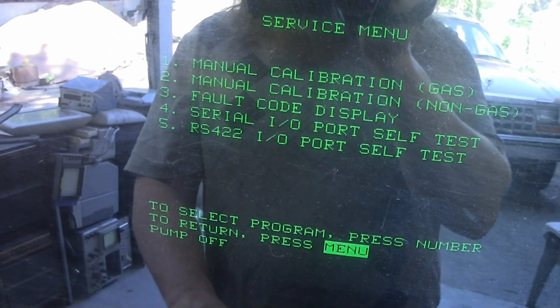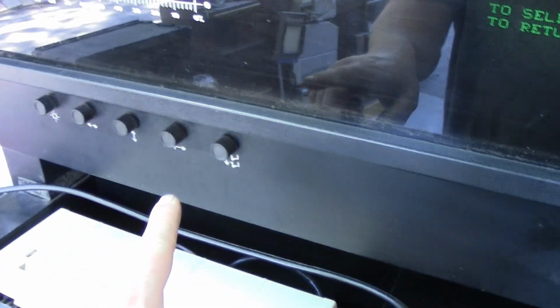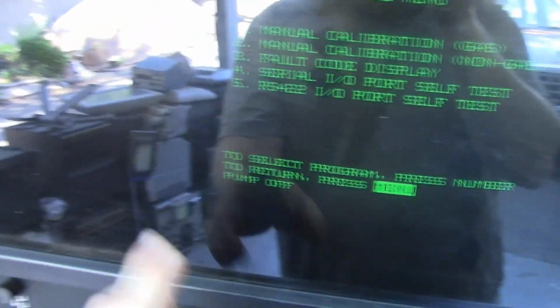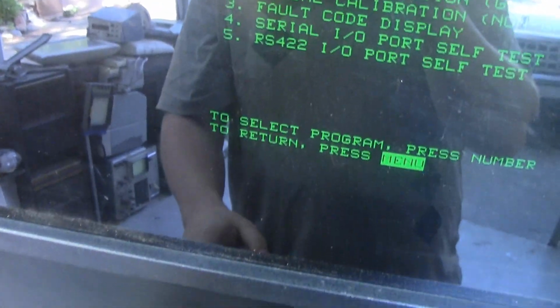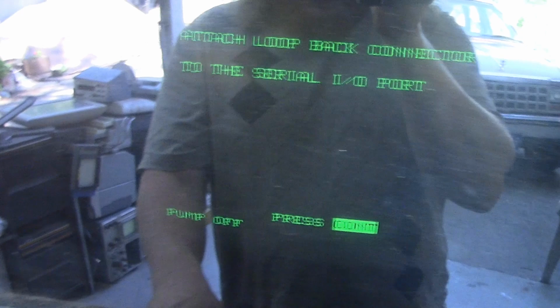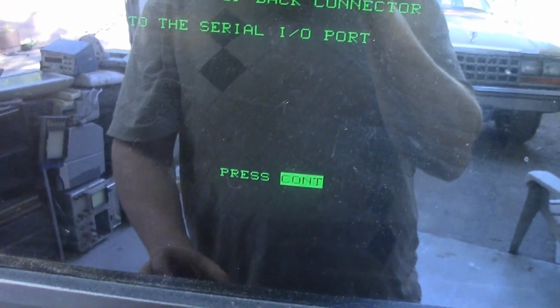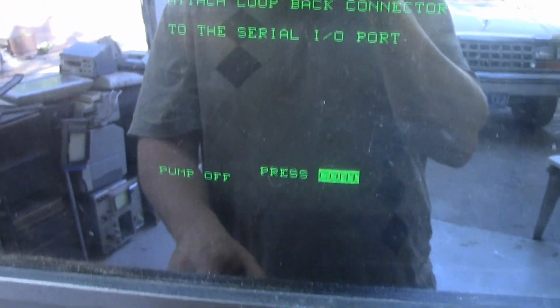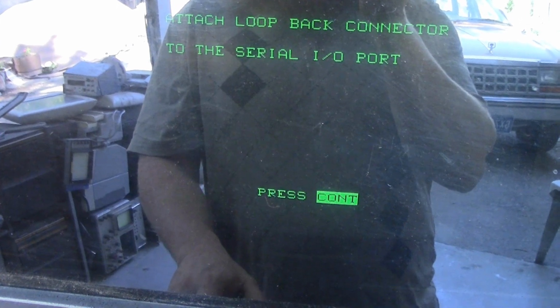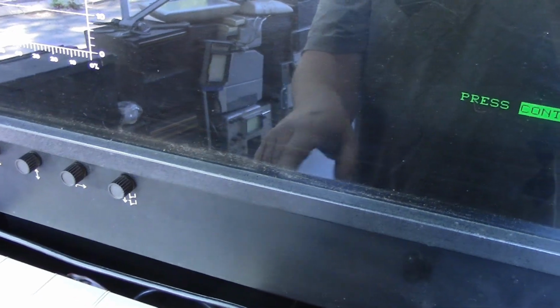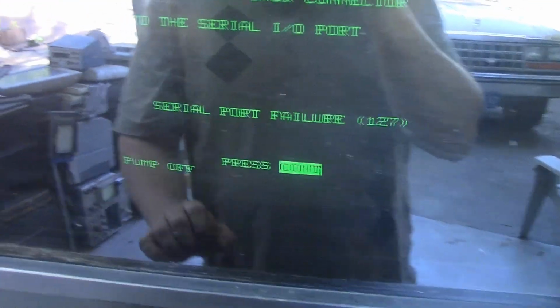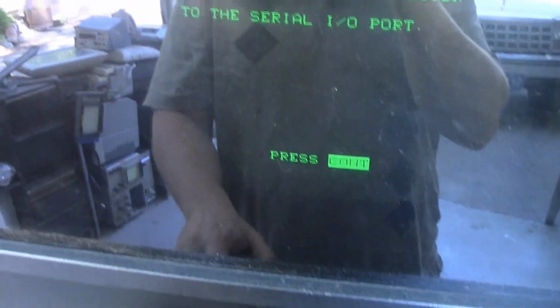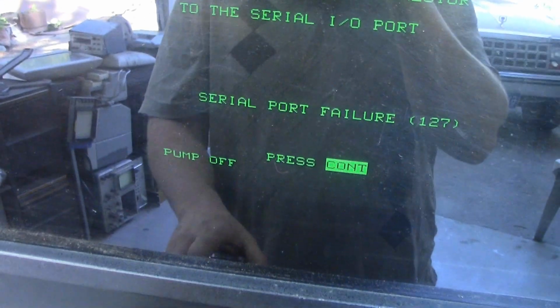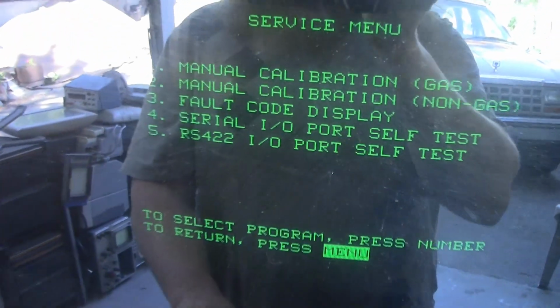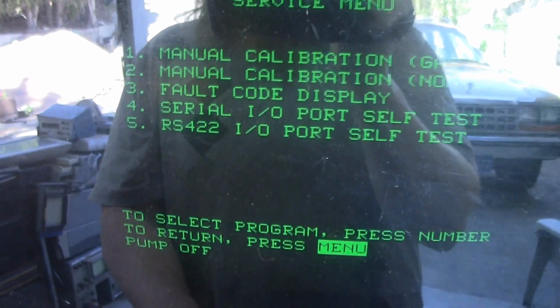And then we have serial I/O port self-test, and that's just simply for the serial port that's on the back of it right now, RS-232. All that's looking for is a handshake. And of course, I can do continue here, and because I don't have a jumper plug installed in it right now, it's going to give me a serial port failure. That's fine. You put a jumper plug on there that asserts CTS and a loopback, that will pass. So I'm going to hit continue again. No, can I go back to the menu? There we go.